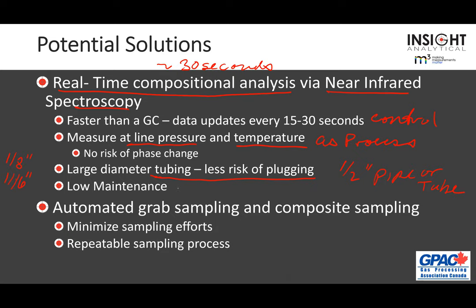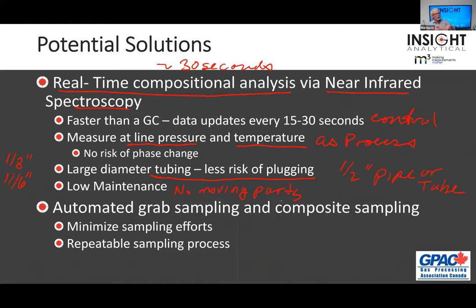Spectrometers let us run through big diameter tubing. Instead of using eighth-inch or one-sixteenth-inch tubing as on conventional analyzers, we run everything on half-inch pipe. So if waxes lay down on the walls or we get sand in there, it doesn't plug off our tubing. And typically we can do all of this with no moving parts. Once we don't have moving parts and things that are going to plug, we don't have much maintenance.